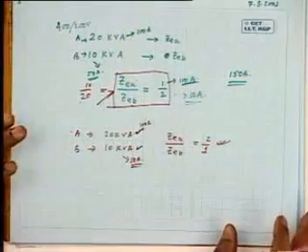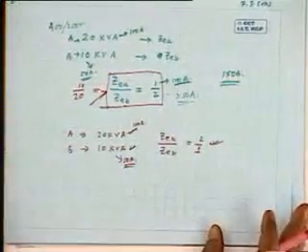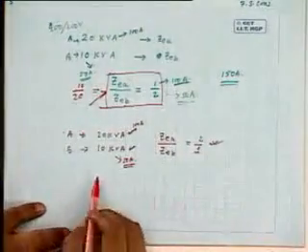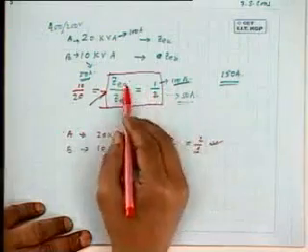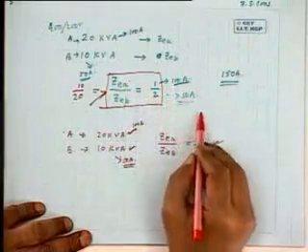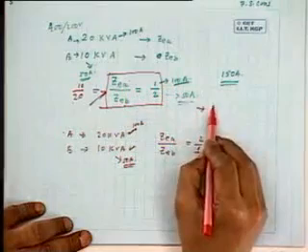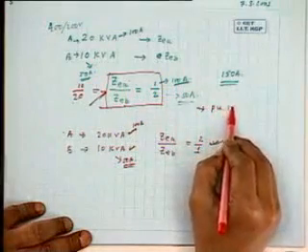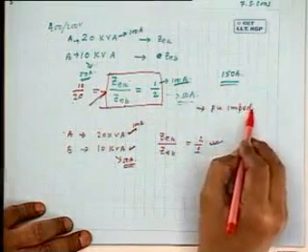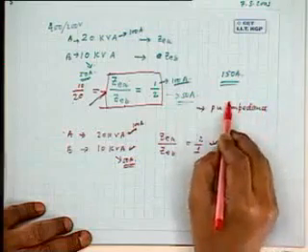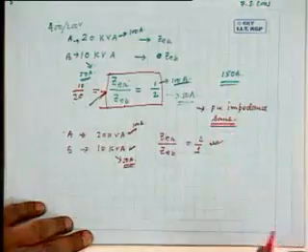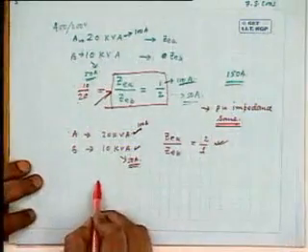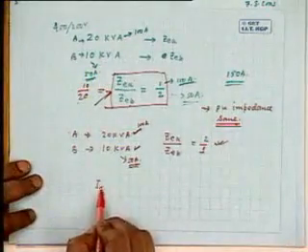Just any two transformers cannot be connected in parallel. At the very beginning, you have to specify this. Obviously, impedances being in the inverse ratio of KVAs will amount to per unit impedances being the same.